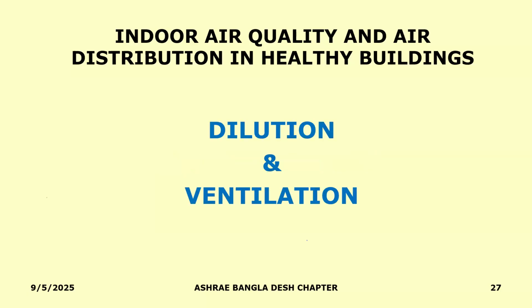The best alternative known to all of us in the HVAC industry is that we can reduce the pollution by dilution and ventilation. So when you say dilution and ventilation, there are several standards that are known to us. You'll find them not just in ASHRAE, but even outside of ASHRAE. Some standards will talk to you about having different air changes for different applications. Some will tell you that you can have a combination of air changes. For example, within ASHRAE, we have ASHRAE Standard 170, which talks about ventilation standards for healthcare environments. And it provides, for different kinds of applications, what kind of air changes you must maintain. If you look at the very recently launched Standard 241, it again talks about air changes.